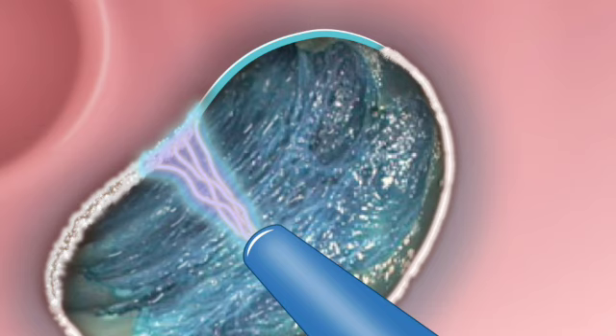Okay, so if we think about this like nozzles on a garden hose, forced APC is twisting it to that hard, continuous jet setting. That's a great way to look at it. But then you have pulsed APC, which alters the delivery. The generator interrupts the gas and the current, creating what Dr. Raju describes as a literal buzz, buzz, buzz effect. Yes, the pulsing. Right. And you have effect 2 for fast, frequent pulses and effect 1 for less frequent ones. So sticking with the hose analogy, this would be the sprinkler setting.